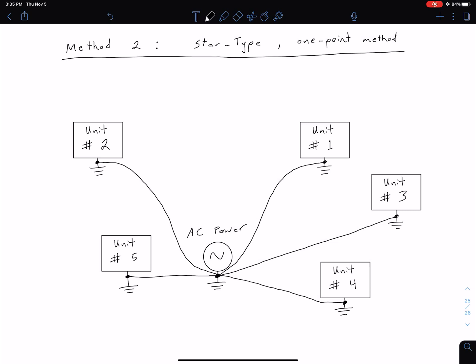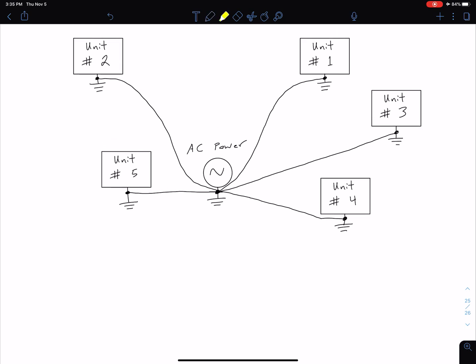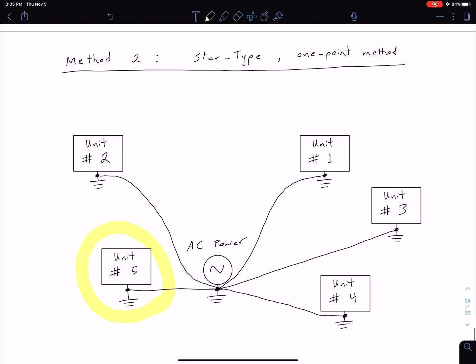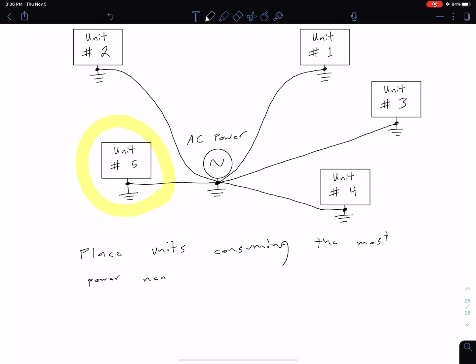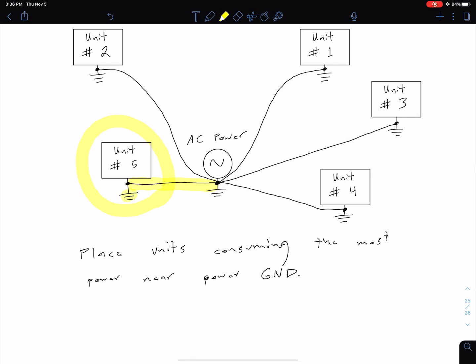Each unit has an independent lead to ground. You'll notice that unit five is placed closer to the source than any of the others. When using the star or one-point connection method, we want to place units that consume the most power closest to the power source ground. The reason is that more power means larger current, and the cabling has resistance proportional to its length, so keeping that length smaller minimizes the voltage drop and lets us approximate both points as being at ground potential.